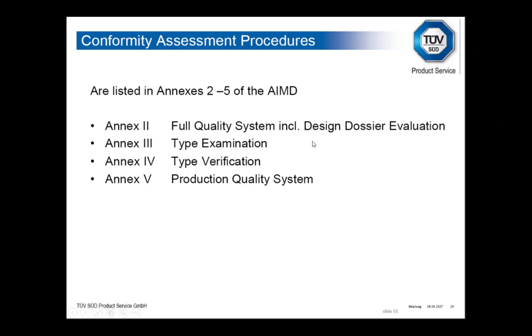And there are other options. If you say, I don't do so many, very small series, you can do a type examination, where you produce something four, five, six times, and then one of those devices is brought to a testing laboratory, and the notified body plays around and makes it explode or something like that to see if it works according to the rules.